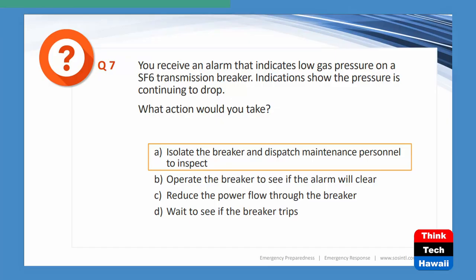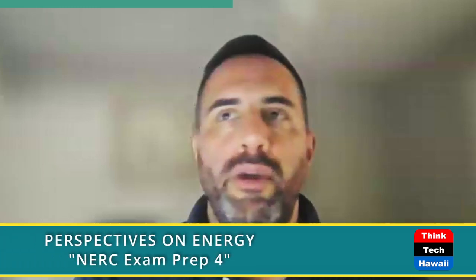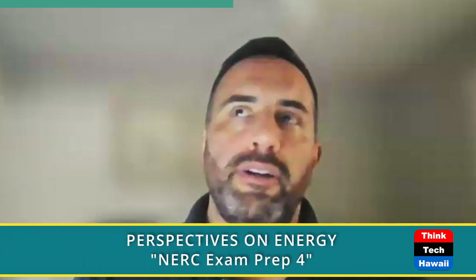So A is isolate the breaker and dispatch maintenance personnel to inspect. So in this case, the sooner you take it out of service and isolate it, the better off you are, because the longer you wait, the less capable that breaker is of functioning reliably and safely. Okay.